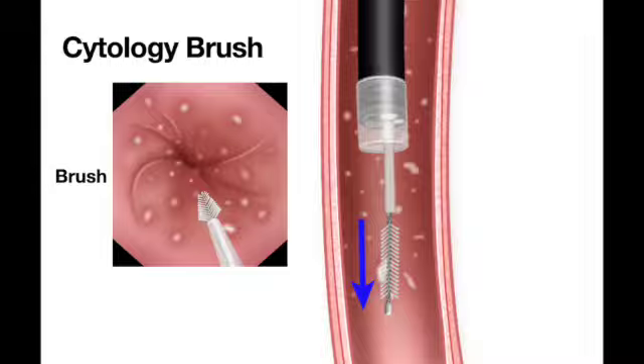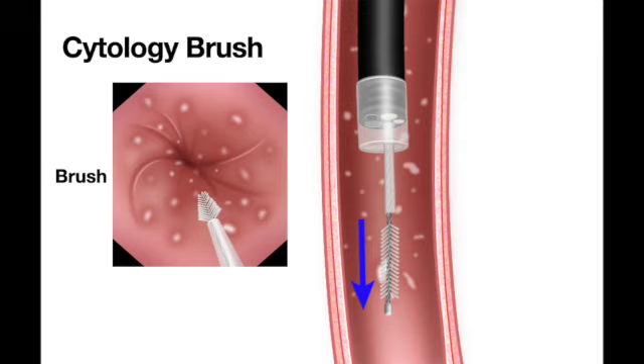No, not at all. The working element of the cytology brush is housed entirely within a flexible plastic outer sheath. That plastic sheath is really the unsung hero of the whole device. It absolutely is. When the assistant unpacks the brush from its sterile envelope, whether it's paper or plastic packaging, the device is in its default closed position. Right. Meaning the slider's pulled back toward the thumb ring, and the brush itself is fully retracted safely inside that plastic casing. So pushing the slider forward, away from the thumb, pushes the brush out of the distal end of the sheath. Right. And pulling the slider back retracts it. Exactly. It's a very simple push-pull mechanism.